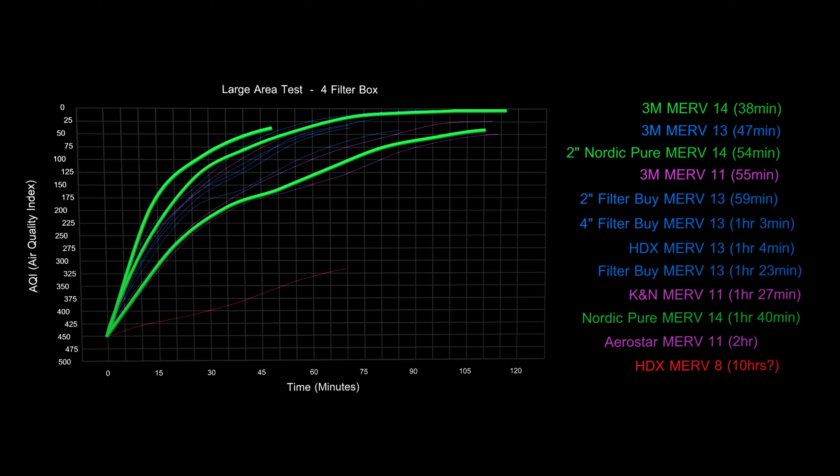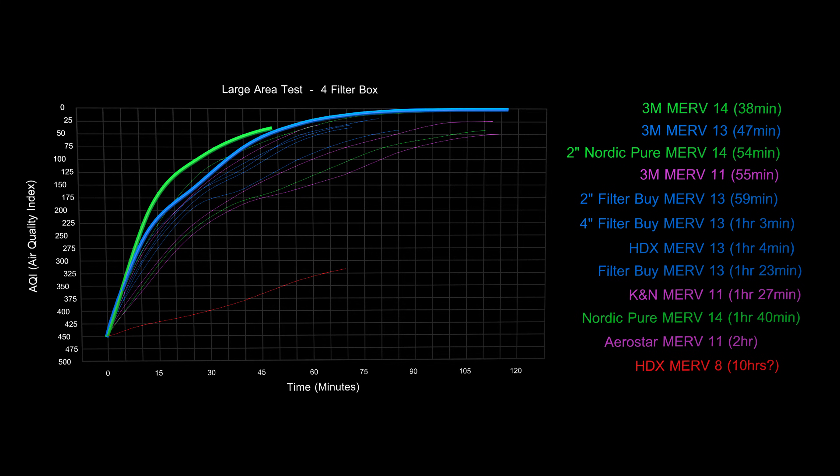Let's look at the top 5 performers across all MERV levels. The 3M MERV 14 filter is easily the best performer, and the 3M MERV 13 comes in second. For a time the 2-inch Nordic Pure MERV 14 was out in front of the 3M MERV 11, but it finished the test at nearly an identical time. The 2-inch Filter Buy MERV 13 met the testing requirements 21 minutes after the 3M MERV 14 crossed the line.